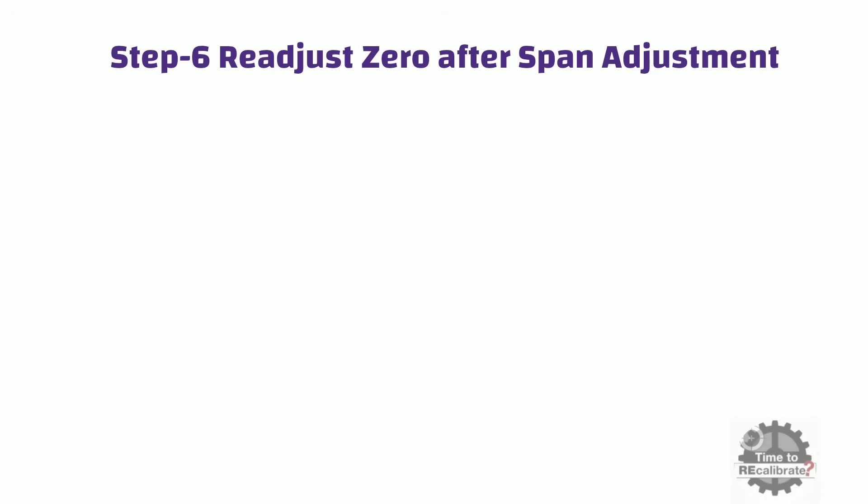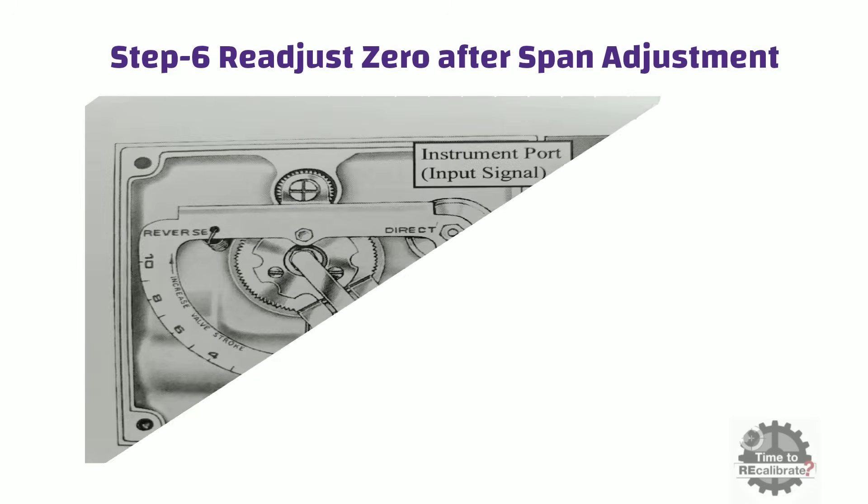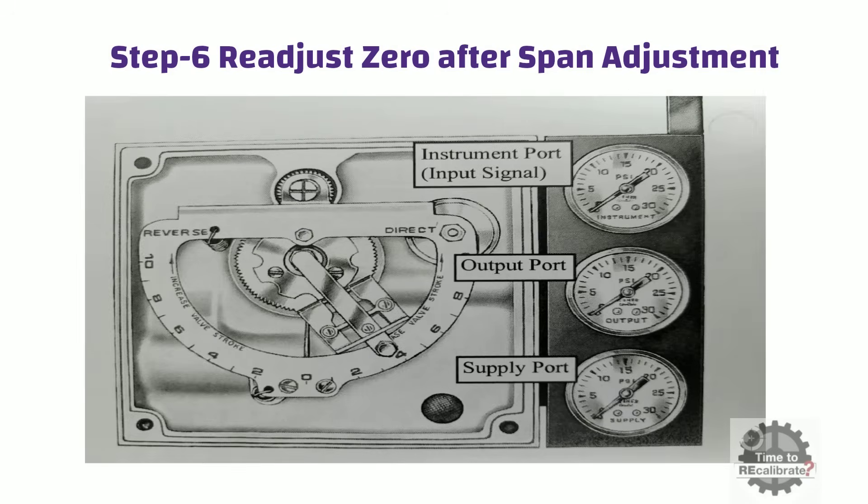Every time you move the flapper assembly, you need to reset the zero adjustment. In order to readjust zero, increase the input pressure to 3 lb per square inch and adjust the output pressure to 3 lb per square inch by rotating the nozzle. After zero adjustment, check the span again.